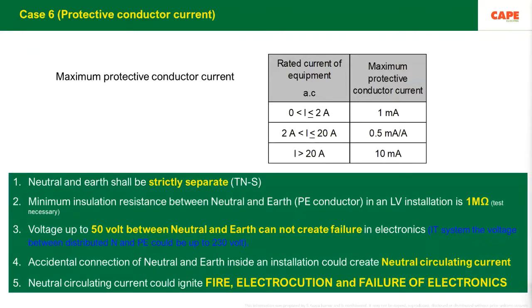Now, case number 6. Every leakage of current from an electrical installation will flow through the earth, that means through the metallic parts of a building; there will be a current flow. Ideally, the current flow through the metallic parts must be 0, but due to leakages there can be a current flow, and this current flow must be limited. Otherwise, it can create a fire.